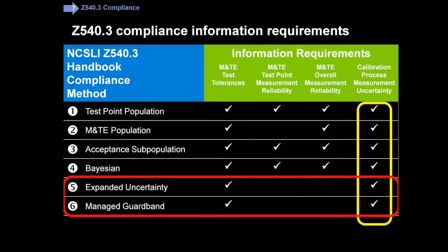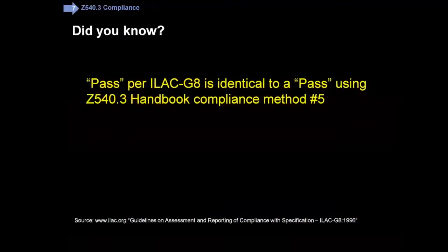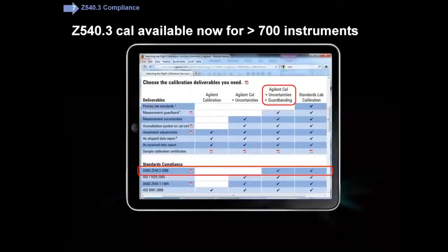At Agilent, the two methods we like to use for meeting Z540.3 are either Method 5 or Method 6. Now, people familiar with ILAC G8 may never have thought about it this way — when we were talking about ILAC G8 and using the Expanded Uncertainty as a guard band, that is what you need for a clean pass using ILAC G8, and it turns out that is identical to Z540.3 Method 5. So Agilent Cal plus uncertainties plus guard banding meets Z540.3 using Method 5.